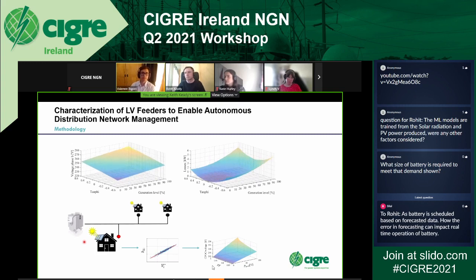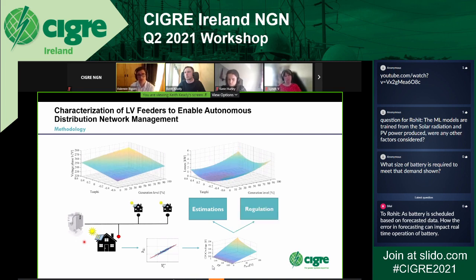So that means that if you know what your PV is doing and you know the local voltage, then you can get this surface, and by a direct calculation, you can then know, this is my estimation of what the voltage at the farthest node is going to be, or what the losses on the system are right now. And at the same time, the idea is that you can then take actions accordingly.